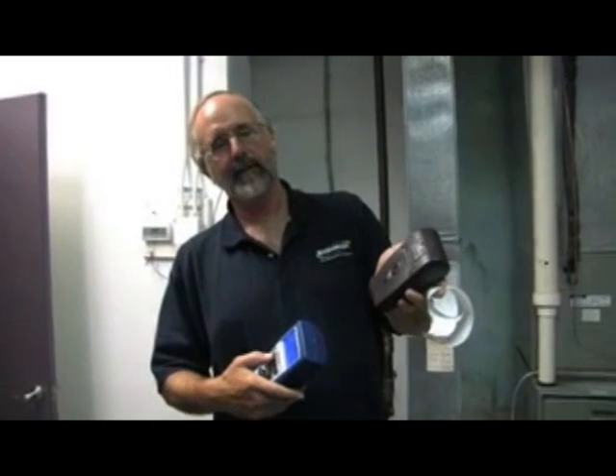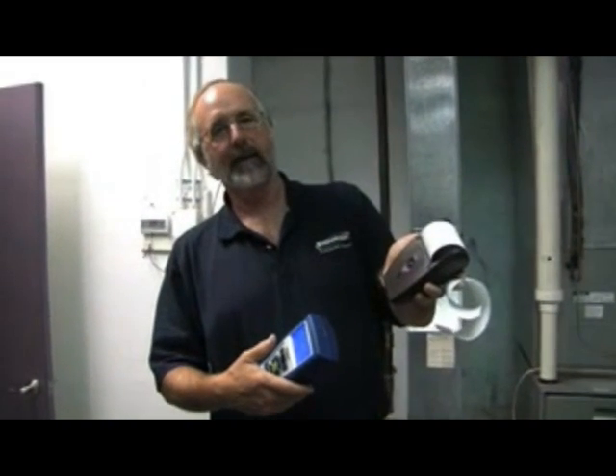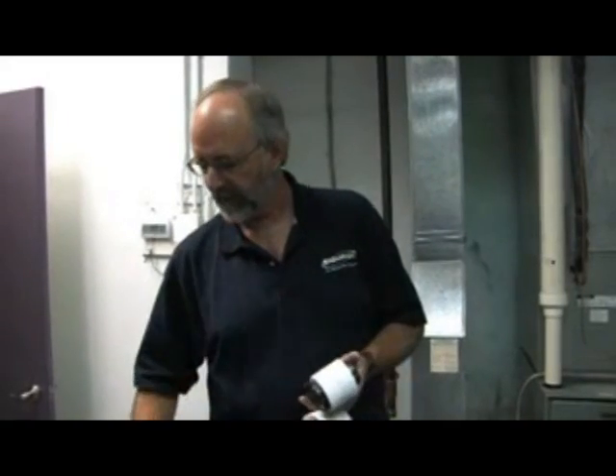Here's a nice feature on this instrument with the infrared printer. I hit F1 and print off the test results. With the new Fyrite Insight, you can put your company's logo on the printer paper. What I do with a customer is show them: here's your original furnace with a 500-degree stack temperature. We can potentially install a condensing unit where you'll have a 100-degree stack temperature — all that extra heat going into the house instead of the stack. Print off two test results, leave them with the homeowner — the original furnace and the new install. Staple them together with your business card. Within a week, you'll be getting calls from the neighbors.